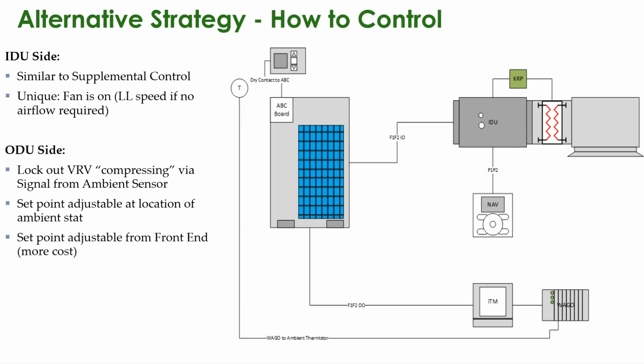How to control this? It's very similar on the indoor unit side. In fact, most of the time you're running the same supplemental strategy on the indoor unit side, right down to the point where you say that it's more beneficial to switch over to gas or whatever other fuel source you're going to use. Similar to supplemental control, on the non-fan required units, the fan coil will switch to a low speed, so you're still able to get some filtration in the space on those wall hung units or ceiling cassettes.